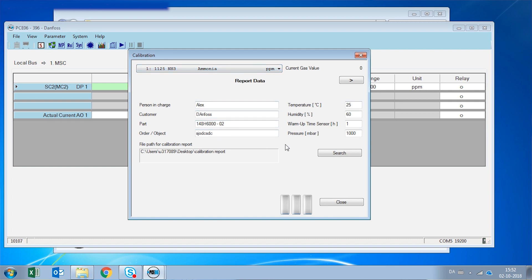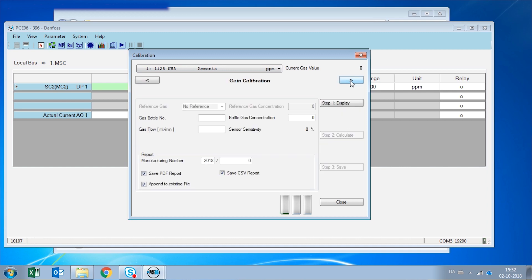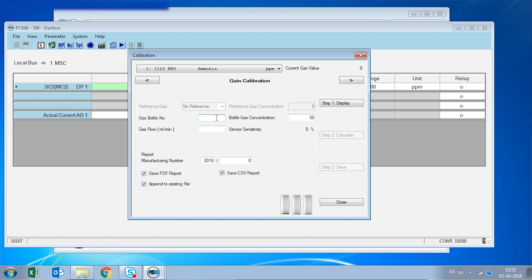We are going to enter all the different information in regards to who is doing the calibration and the different conditions. And if we follow on these screens, we are going to get to the part where we are going to have to enter the concentration, which in this case can be 50 ppm. We can put the serial number of the bottle, the flow that we are administrating to the detector. And if we calibrate by this means, it's going to create a PDF report of the calibration.